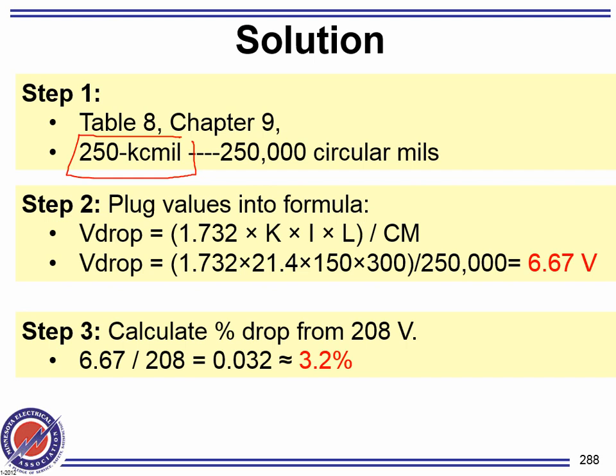So here's your voltage. Is this voltage good, bad, or ugly? How do you know? You have to divide it by which voltage, the 208 or the 120? The 208. And you get 3 point something. Is this bad? Yes. Why? Higher than 3. What would you do to mitigate the situation? You go to the next standard size. You go to 300 kcm and recalculate again and see what you come up with. Most likely you're very close. If you go to 300, you will make it.